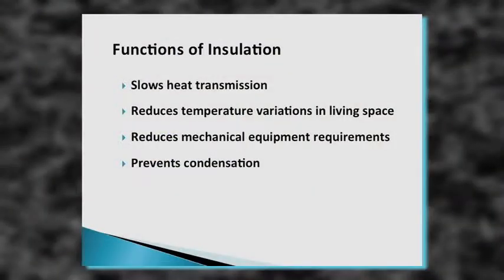Insulation also prevents condensation. If our walls stay warmer, the air next to the walls stays warmer and the relative humidity near the walls stays lower — compared to uninsulated walls where the surface might be 30 degrees and condensation would form.